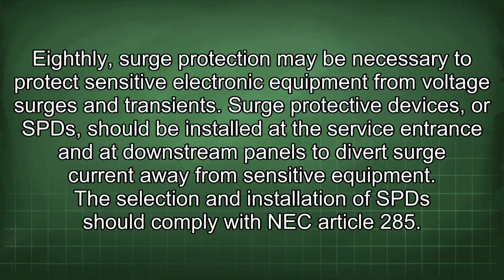Eighthly, surge protection may be necessary to protect sensitive electronic equipment from voltage surges and transients. Surge protective devices, or SPDs, should be installed at the service entrance and the downstream panels to divert surge current away from sensitive equipment. The selection and installation of SPD should comply with NEC Article 285.